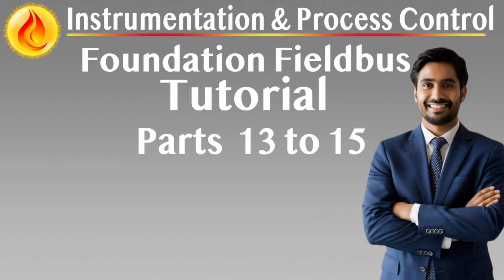Power and intrinsic safety design is another planning essential, especially for hazardous area installations. Engineers must determine if conventional FISCO, FNICO, or entity models are to be used and size power conditioners accordingly. Device current consumption, cable impedance, and segment termination must be calculated to maintain compliance with voltage and current limits while ensuring stable operation. Where necessary, field barriers and segment couplers must be specified and their locations integrated into the layout.